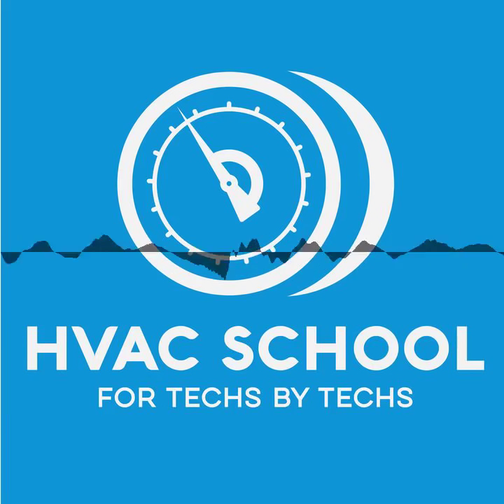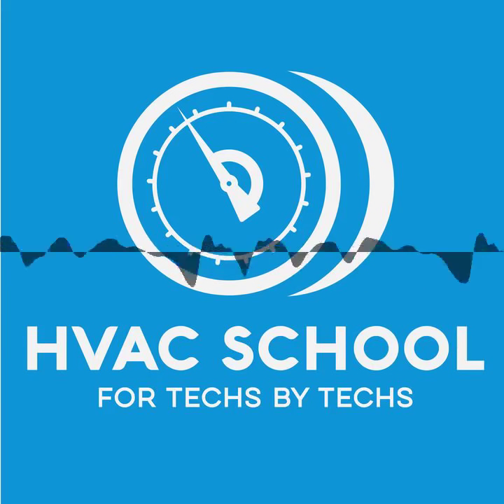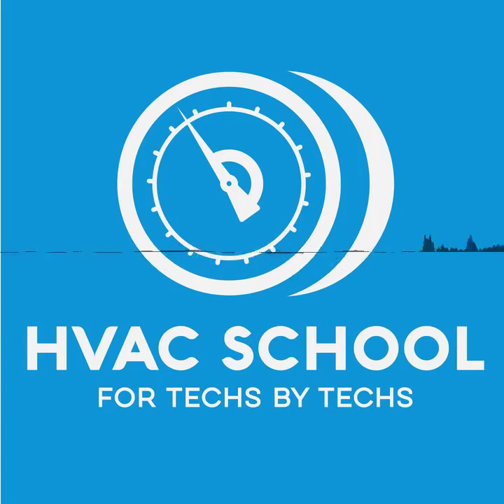Also, if you work on ductless, one thing that a lot of people struggle with is testing performance on a ductless system, because checking the charge is really tough on ductless. I mean, you can tell if the thing's flat, but other than that, it's tricky because there are so many moving parts. But what you can do pretty easily on most ductless systems is you can get a chart that shows you the different CFM output for the different stages of operation.